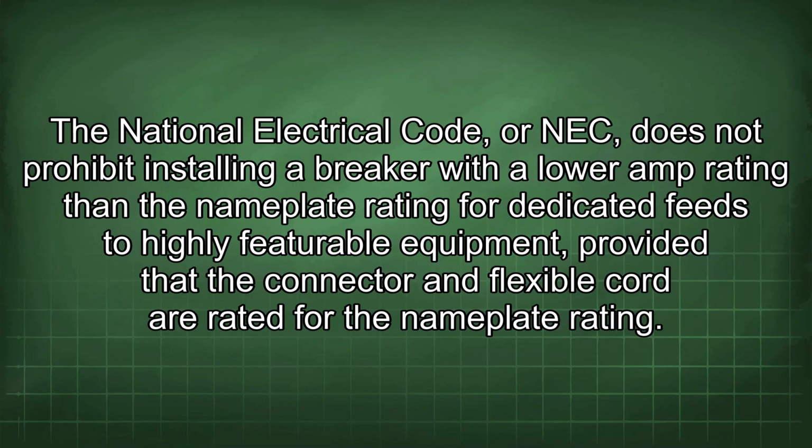The National Electrical Code, or NEC, does not prohibit installing a breaker with a lower amp rating than the nameplate rating for dedicated feeds to highly configurable equipment, provided that the connector and flexible cord are rated for the nameplate rating.